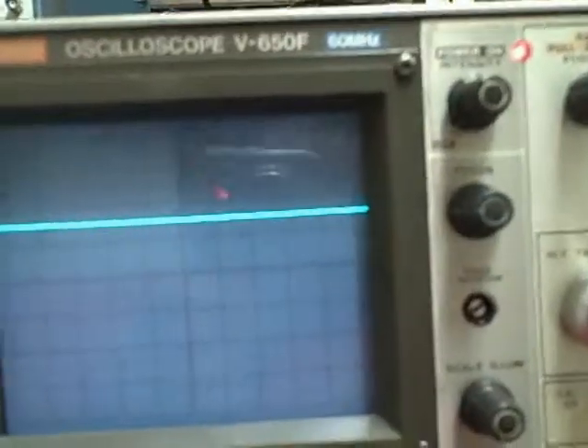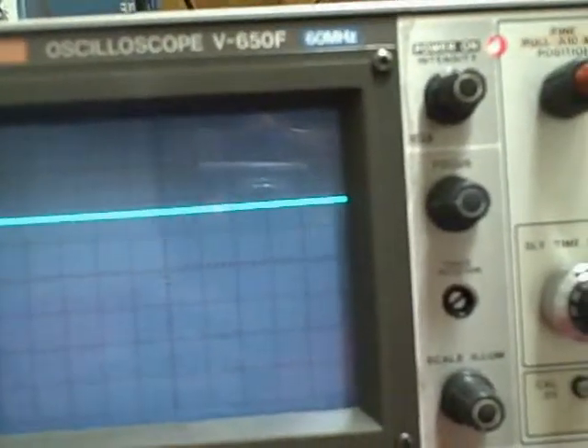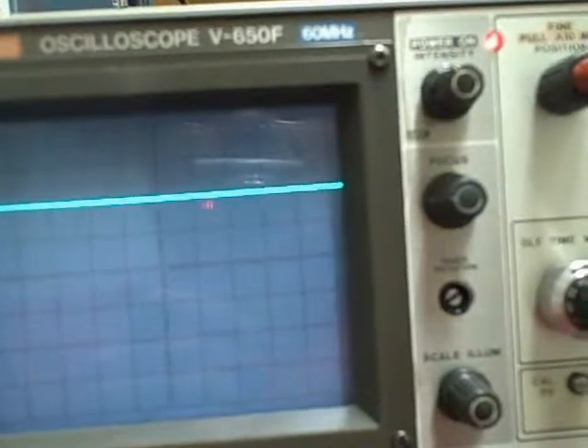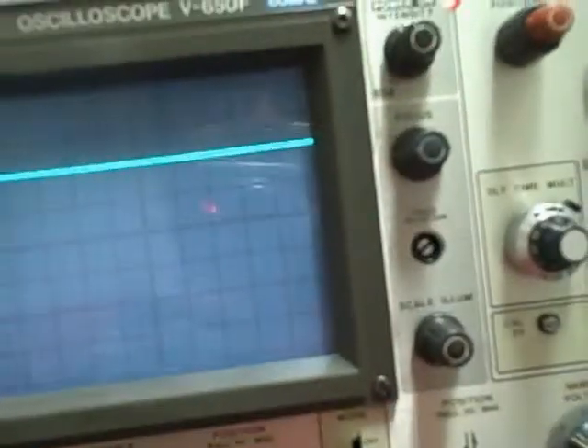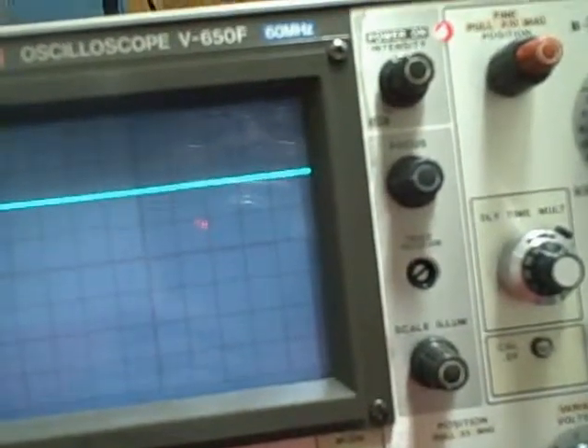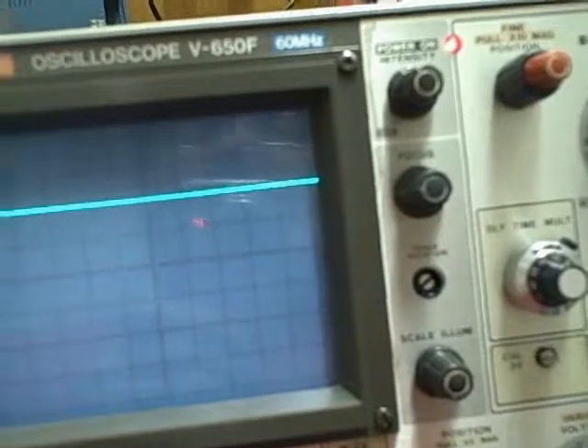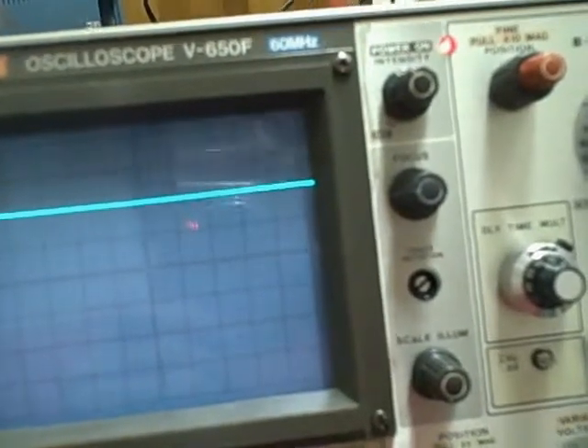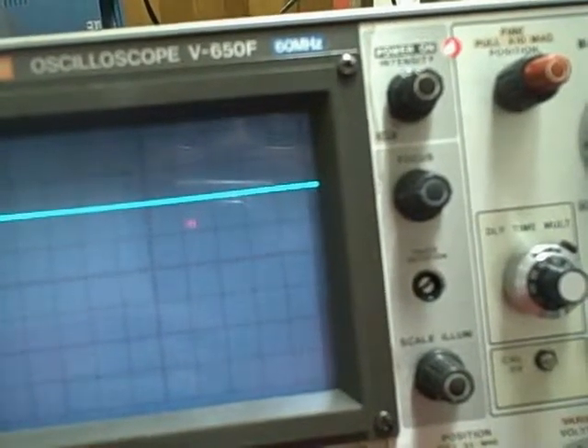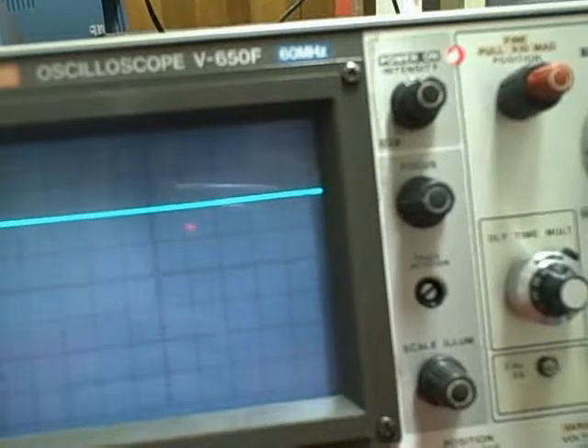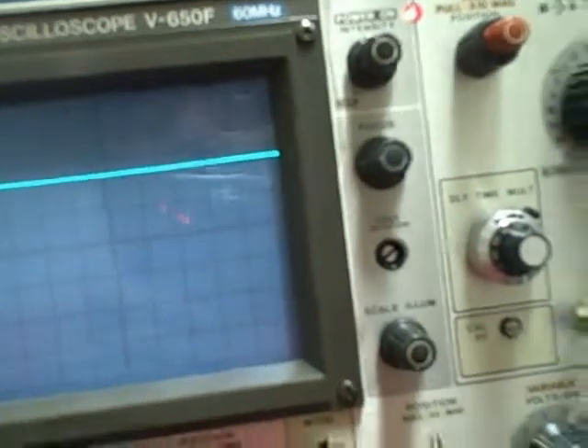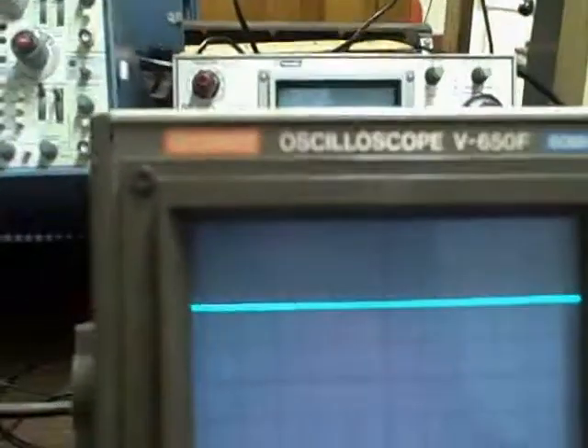0.5 volts per division, we see the one and a half divisions again. Let's go ahead and raise her to 2 and put ourselves at 2. Let's say we are 2 right about there. So we should be reading 1 volt. We are reading 1.02 volts, so 0.02 volts off. Not bad.